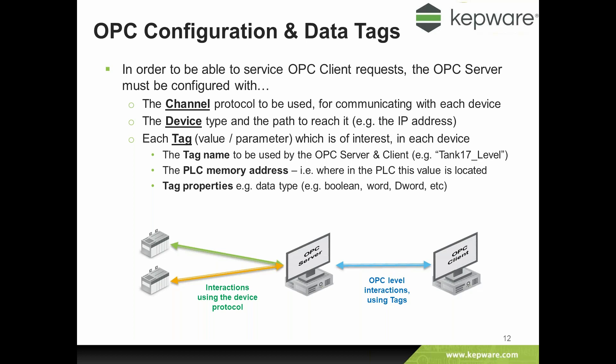Then the list of tags can be added to the configuration. These are the values within the PLC which are of interest to the client applications. Each tag has a name that is meaningful in the client application — for example, 'Tank17_Level', which would be the level in tank number 17. The OPC server must know how to reach the correct PLC address to get that value, so each tag has a PLC memory address allocated to it, along with other properties such as the data type — whether the tag is a boolean (one or zero), a word, a Dword, or other data types.